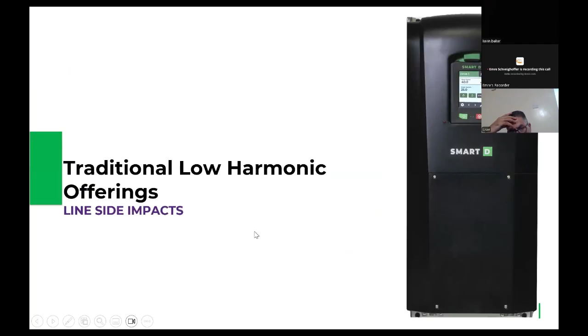So a traditional standard VFD will have a diode bridge, of course, that rectifies and brings this wonderful AC wave and turns it into a DC. And then it'll turn around and finally chop up that DC signal with these switches called IGBTs. And that results in a square wave going out to the motor. It doesn't look like a sine wave, but it's trying to simulate a sine wave, as we all know. So there's loss of energy at rectification, and then there's also loss of energy in having a simulated sine wave.